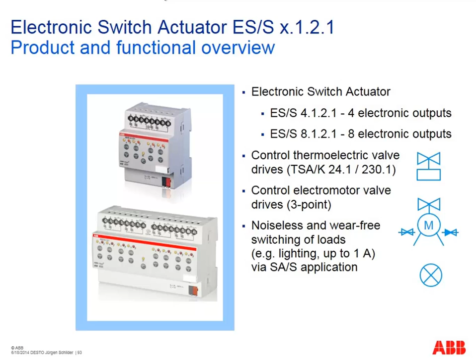And you see here the connection diagram as an example. Channel A connected to an electrothermal valve drive. So one channel necessary only. Channel B, lamp load. The next channel. And channel C and D now in use for operating a motor valve drive. Keep in mind, then you need two channels because we have two inputs in such a motor, for opening and for closing. So two contacts are necessary. Operating voltage can be 24 or 230 volt AC/DC, you will see later on in the summary.